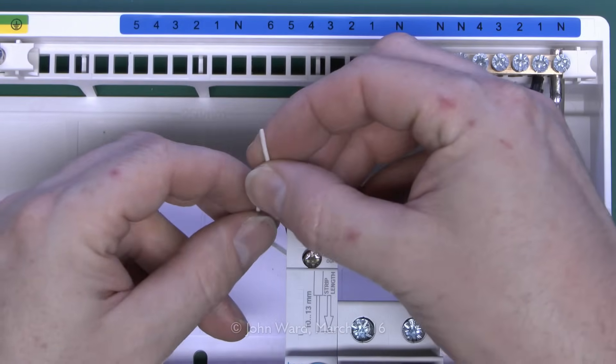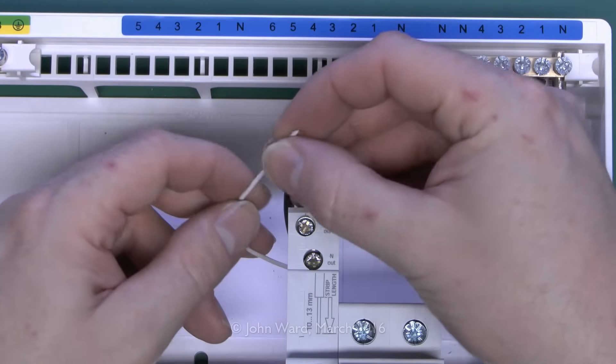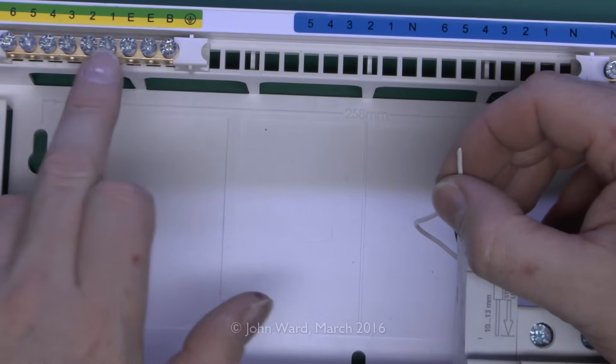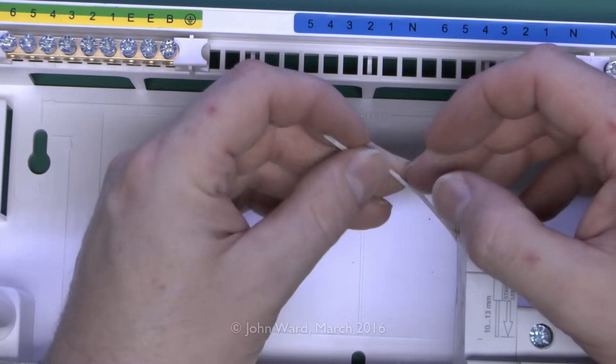The other thing to remember is that if it has one of these functional earthing leads here which is either white or cream colour then you just need to connect these over to the earthing bar here at the top. Unfortunately this one this has been cut off as it's been removed from an old installation but normally they're plenty long enough to reach to the bar over there.